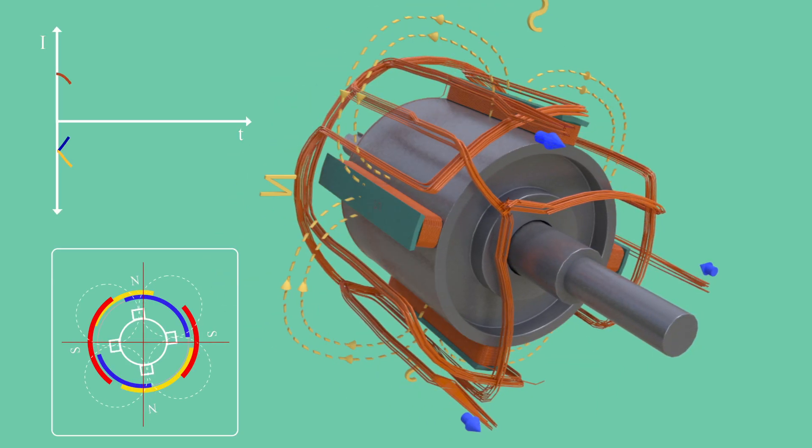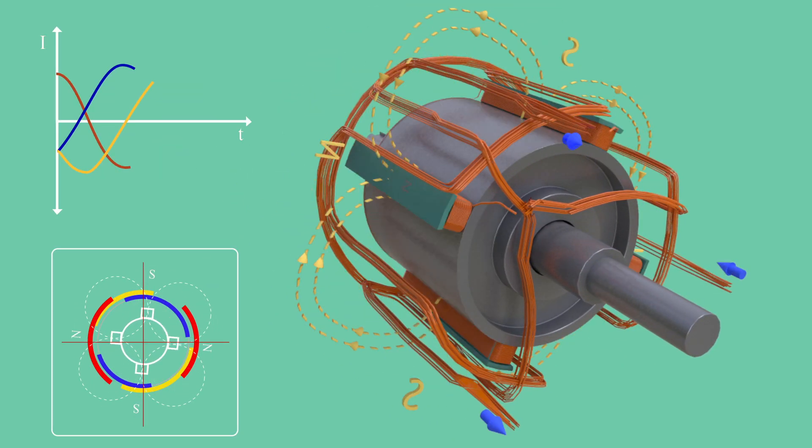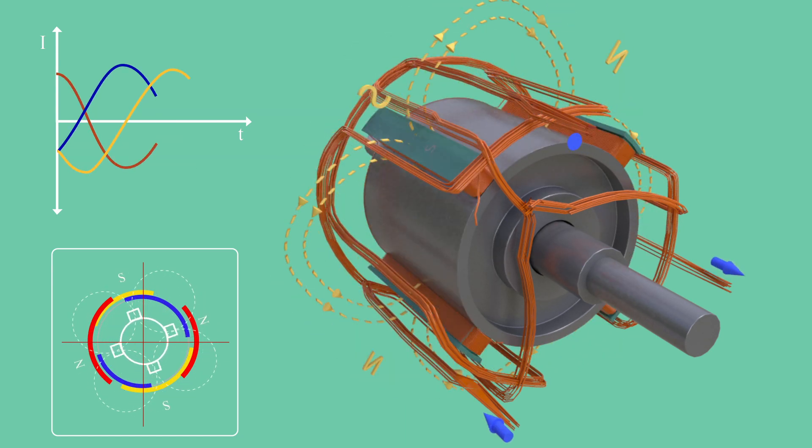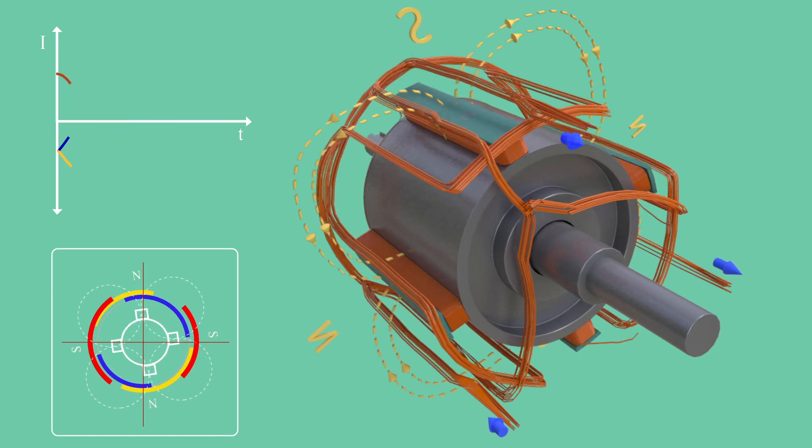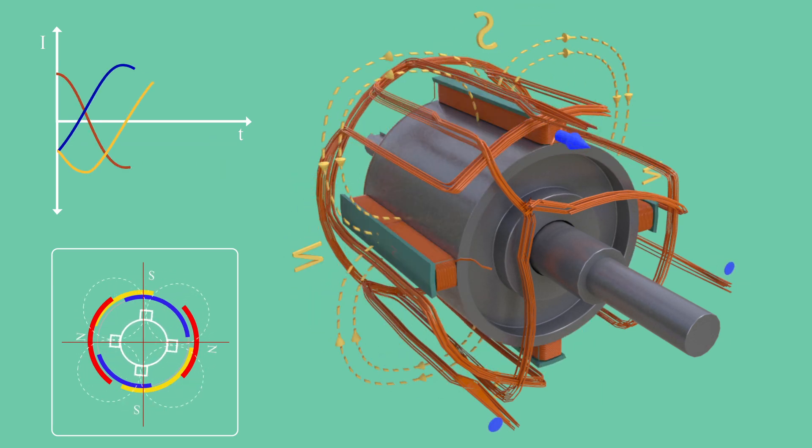It is clear from the past equation that in order to produce 60 hertz electricity, a four-pole rotor should run at a speed of 1800 RPM.